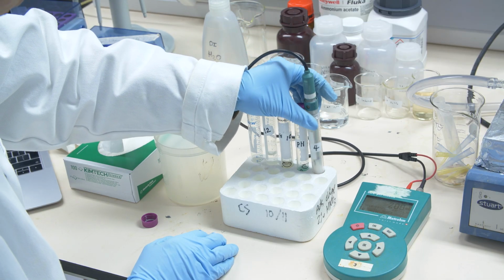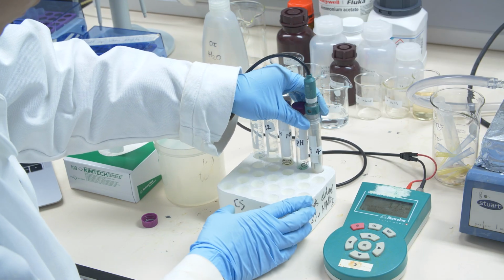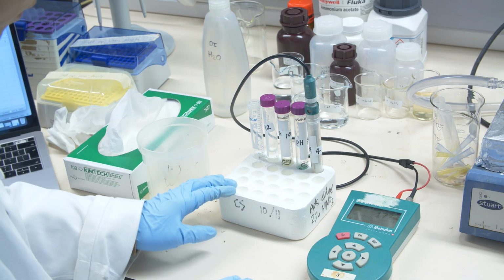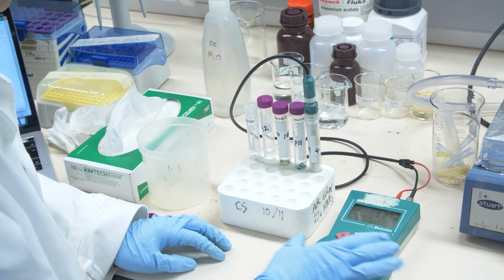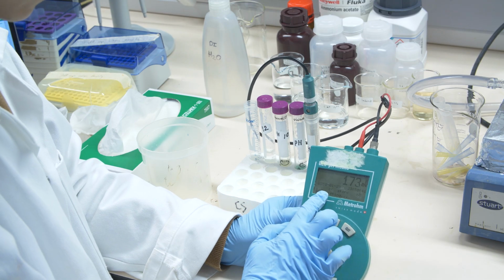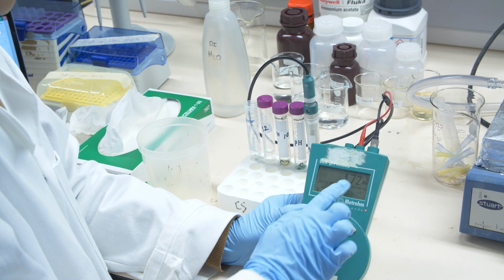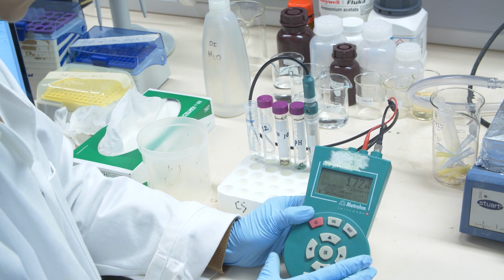He takes it out of the storage solution, rinses it very well with water, takes the water off very, very gently with the paper, and then puts it in the first calibration standard. And you see here that it has a potential of 172 millivolts in the pH 4 calibration standard.